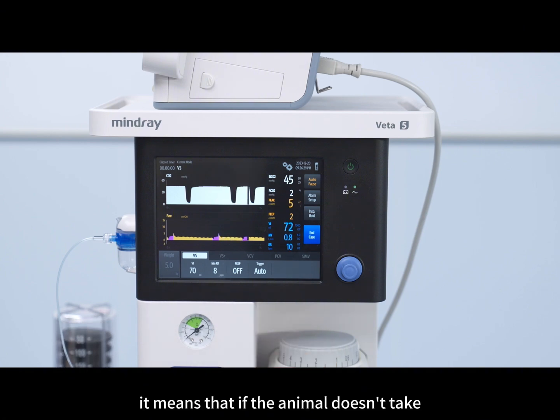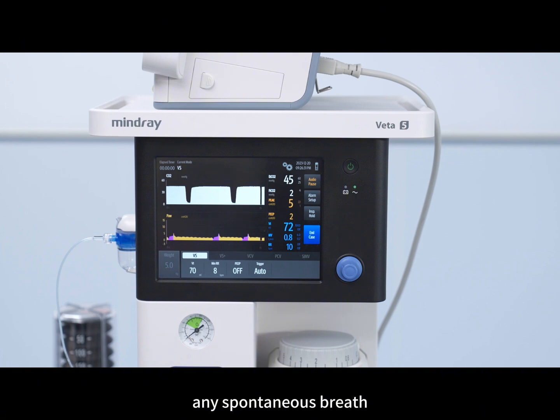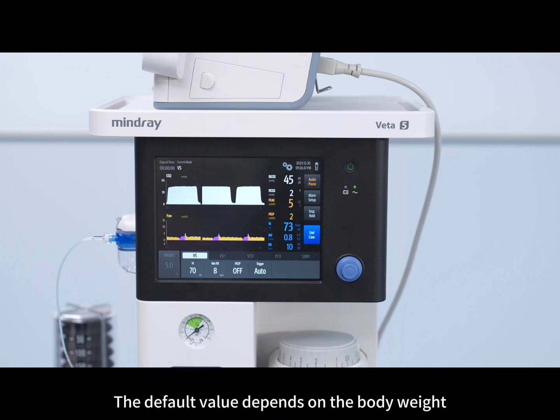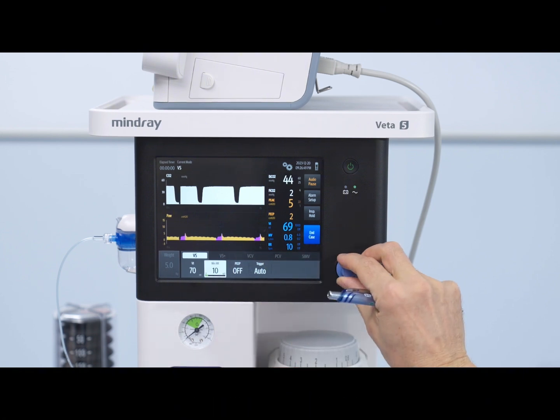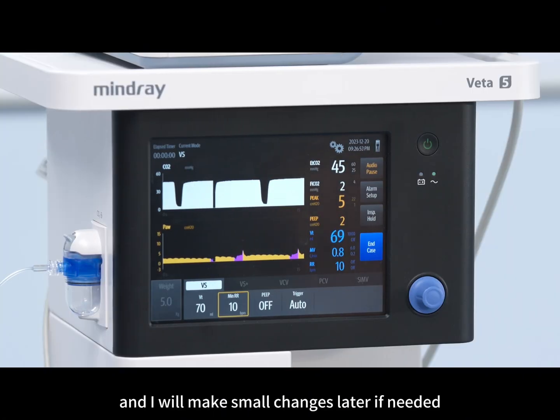It means that if the animal doesn't take any spontaneous breath, the ventilator will give at least this number of breaths per minute. The default value depends on the body weight, but it ranges from 4 to 8 breaths per minute. I usually increase this number to 10 as soon as I start my case, and I will make small changes later on if needed.